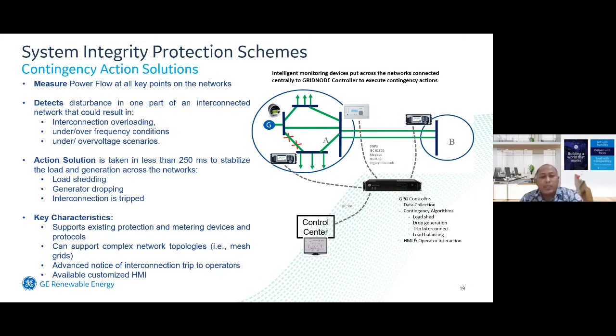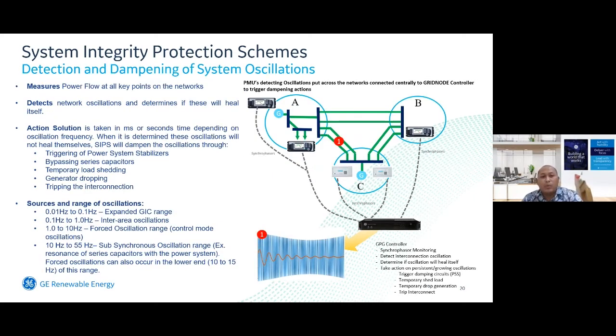So here is the second solution related to our SIPS solution. This is related to detection and dampening of system oscillation. So how does the system work? It measures the power flow at all key points on the network. It detects the network oscillation and determines whether the system can heal by itself or not.